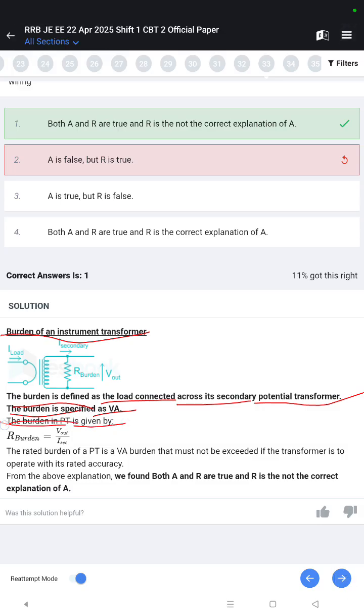Burden of an instrument transformer. The burden is defined as the load connected across its secondary, for a potential transformer. The burden is specified in volt-amperes. The burden in a PT is given by R burden equals V out by I secondary. The rated burden of a PT is a volt-ampere burden that must not be exceeded if the transformer is to operate with its rated accuracy.